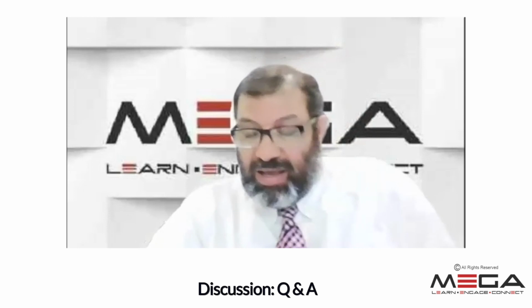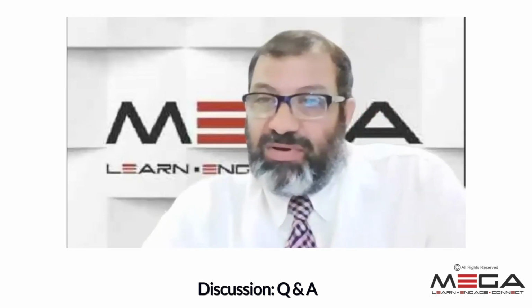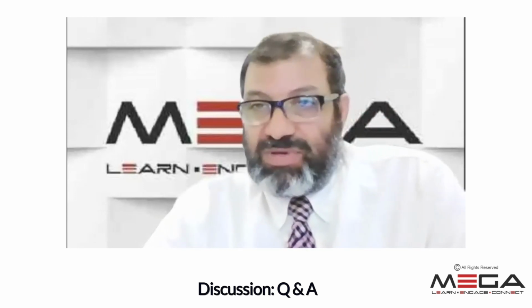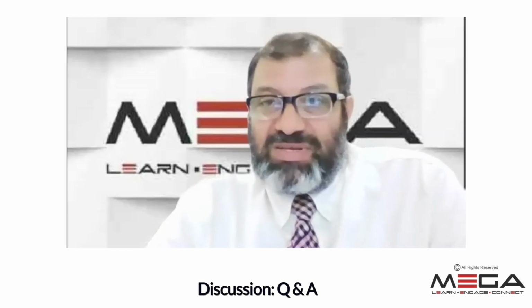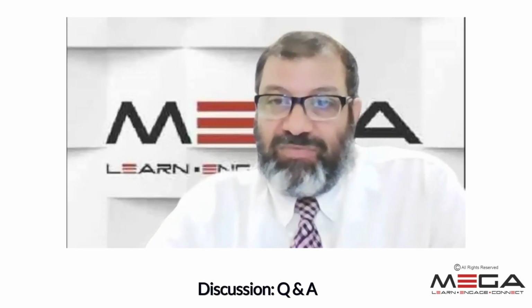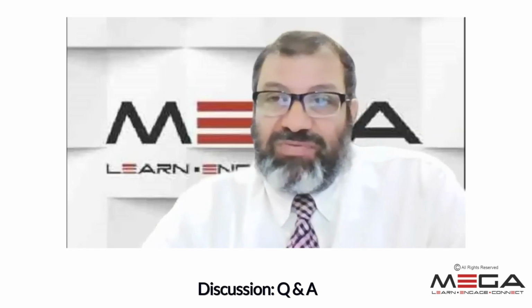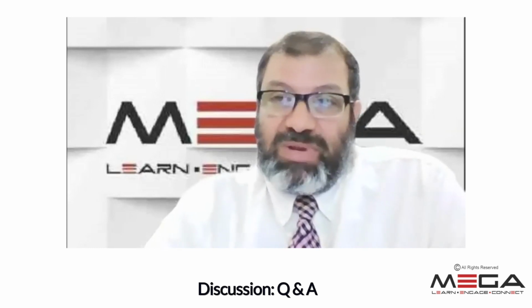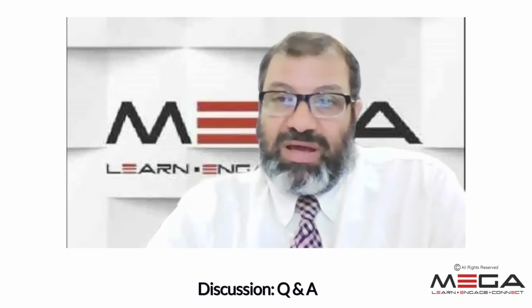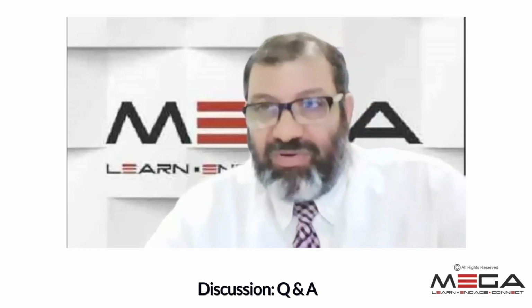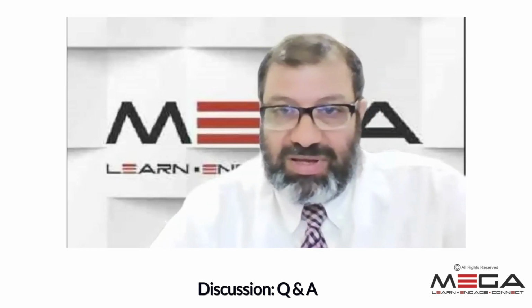Thank you. Again, you speak about the preset volume and the real volume which comes into the patient. What is the permissible difference we can accept in our ventilator? For example, if I adjust it for 500, what can I accept for this ventilator when it goes to the patient, for example, 400, 450 or more? Yes. In my opinion, it is not written anywhere in the literature, but in my opinion, it is within 10% of the preset tidal volume.